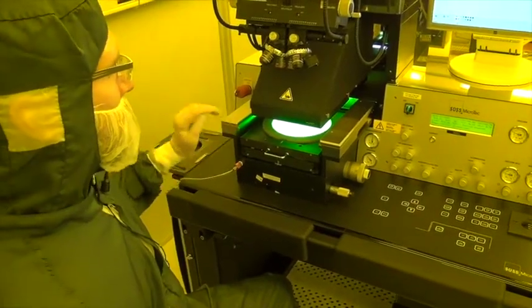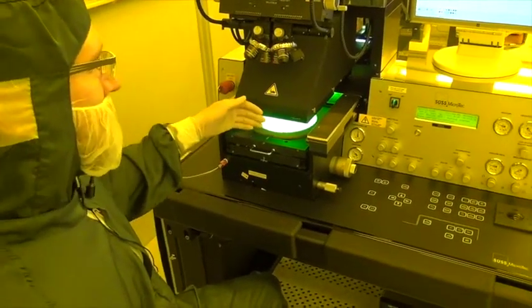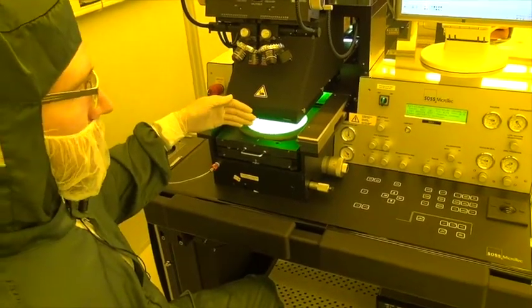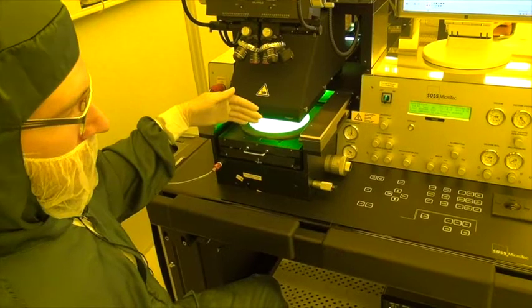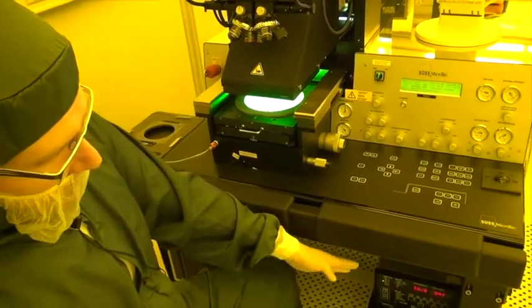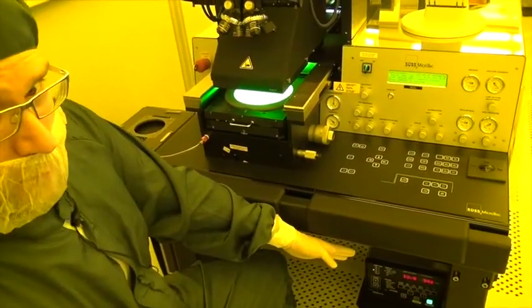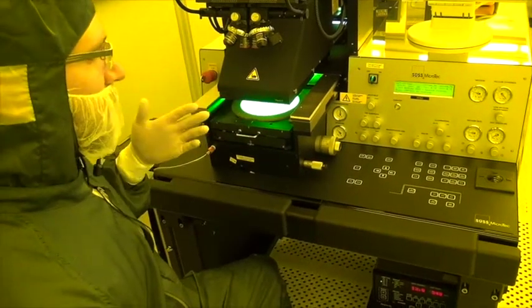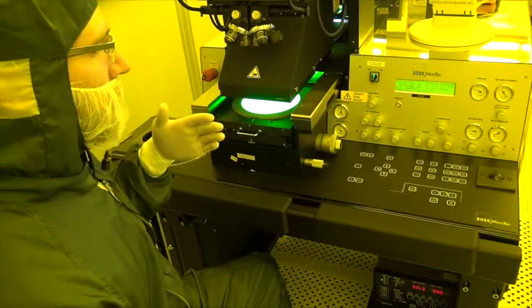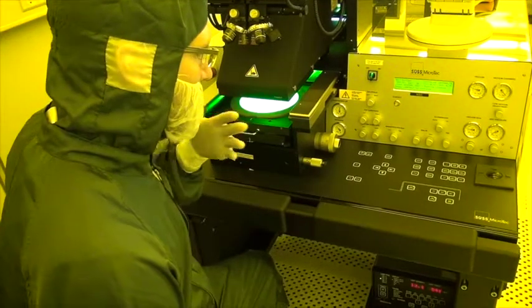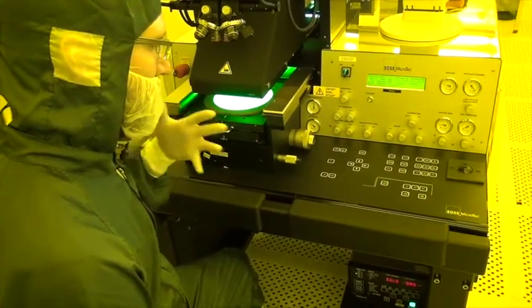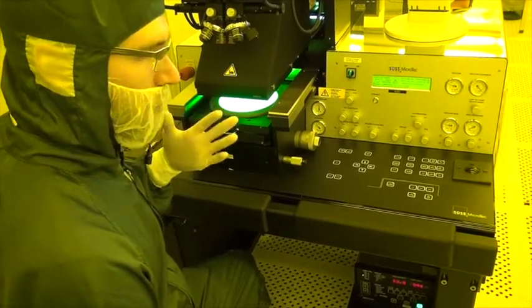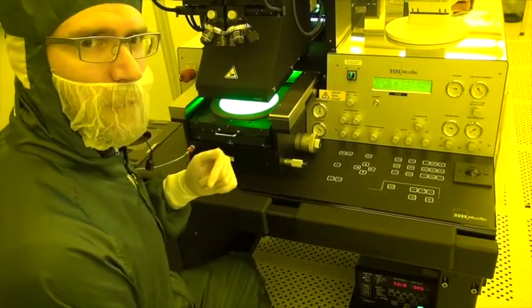In terms of safety, the intensity of the light that's scattered here at the front of the lens is about a factor of 50 lower than the intensity we see down here on the power supply. And once we move away from this it drops rapidly. And when we come out here where the operator's face normally would be it's at least one thousand times lower, which is perfectly safe.